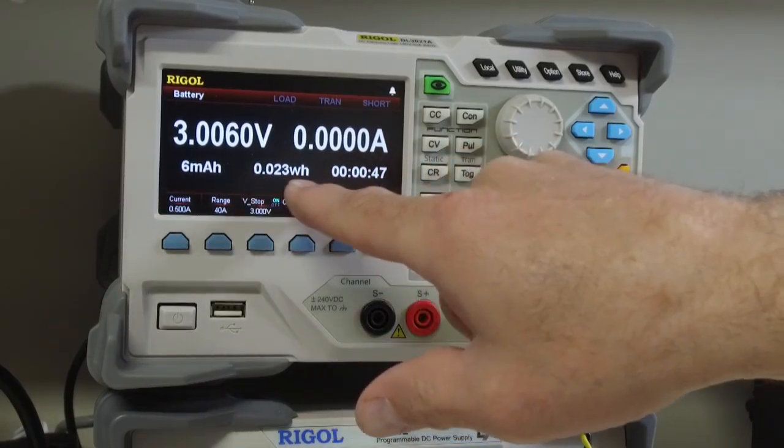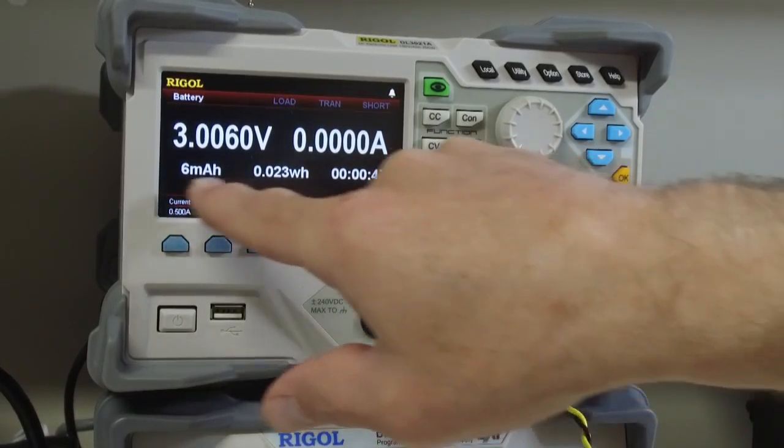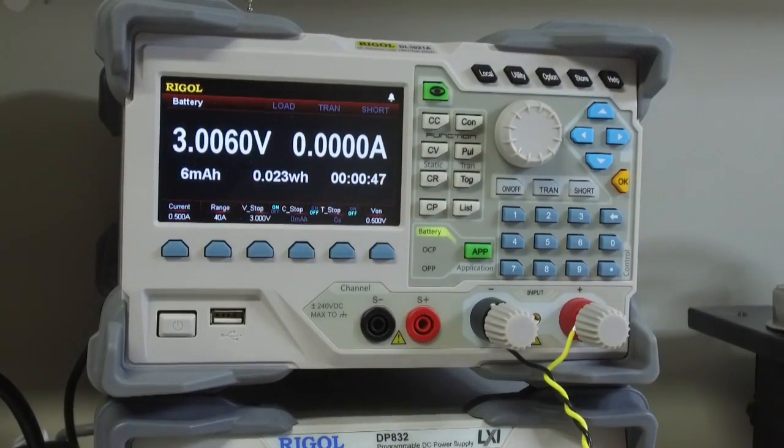And simulate that the battery capacity is lowering because the voltage is lowering. I'm going to keep on clicking that down. And it says battery test completed because it dropped down to the 3 volts. And the timer stopped. And it told us, is now telling us that our battery capacity is this many watt hours or this many milliamp hours. Pretty slick feature.